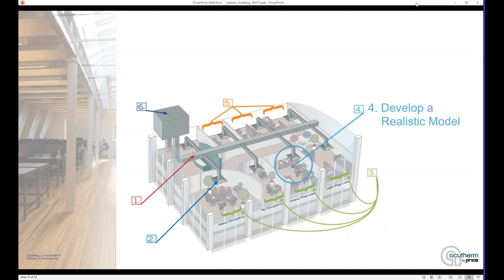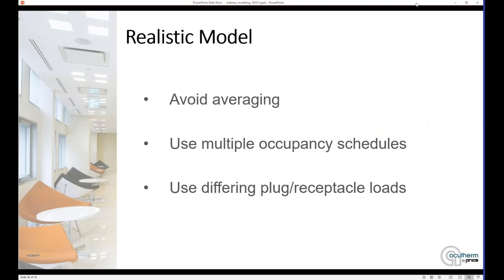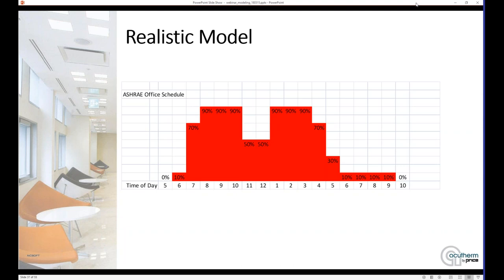This is a good lead into our next point, which is developing a realistic model. Just like high-load spaces, there are other load shifts within the building, and you want to try to avoid all that averaging because the building doesn't have one consistent load throughout. The energy modeling works in things like sun load, but we need to also put in things like our occupancy schedules and plug receptacle loads, and make sure those make sense for the building. These also help when trying to show a realistic model, especially with a Thermafuser diffuser system because of those small zones of control.